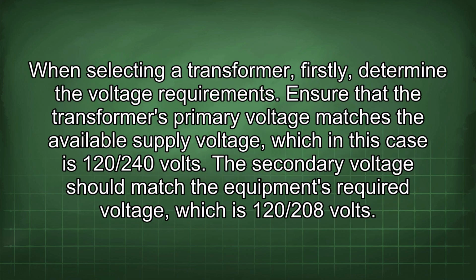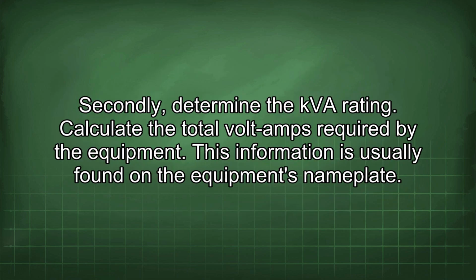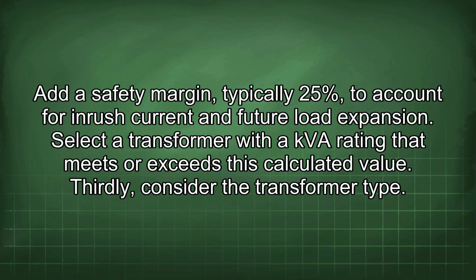When selecting a transformer, firstly determine the voltage requirements. Ensure that the transformer's primary voltage matches the available supply voltage, which in this case is 120/240 volts. The secondary voltage should match the equipment's required voltage, which is 120/208 volts. Secondly, determine the kVA rating. Calculate the total volt amps required by the equipment. This information is usually found on the equipment's nameplate. Add a safety margin, typically 25%, to account for inrush current and future load expansion. Select a transformer with a kVA rating that meets or exceeds this calculated value.